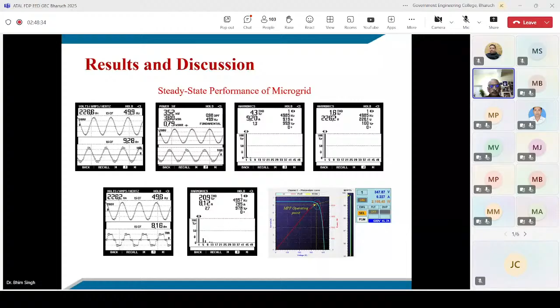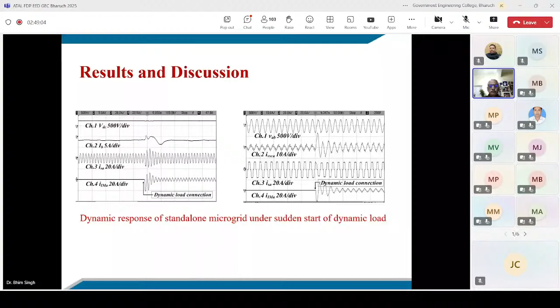You can see motor starting here, which does not affect things too much. Looking at the voltage, it is not too much affected when a dynamic load is connected, because it will draw a larger inrush current of the motor, but the voltage remains unaffected. The converter takes care with the battery of this inrush, but the load voltage is not affected. The battery handles high power consumption and takes care of dynamic load variation as well as the nonlinearity of other loads.